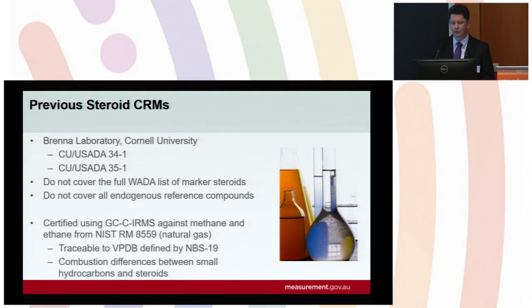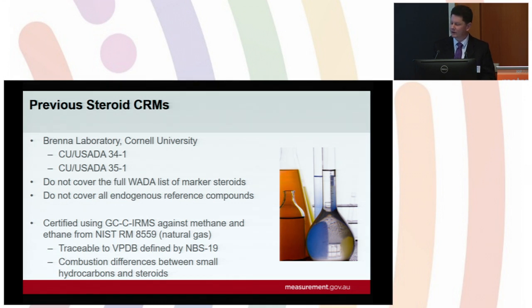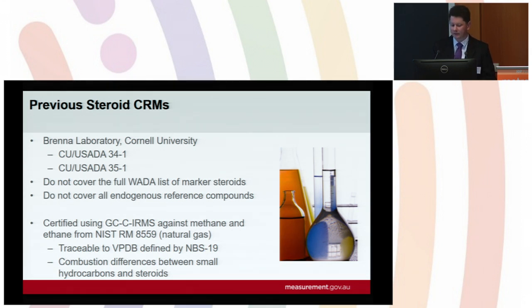NMIA is not the first group to produce steroid CRMs. They originally came out of Professor Tom Brenna's laboratory from Cornell University. The two most relevant products are the USADA 34 and 35 materials, which don't cover the full list of marker steroids specified by WADA nor the full list of endogenous reference compounds. These materials were certified by GC combustion IRMS against a methane and ethane natural gas reference material, only traceable to NBS19, not the current NBS19/L-SVEC scale. There are also combustion and chromatographic differences between the light hydrocarbons and the steroids, which give us scope to produce a material of higher order.